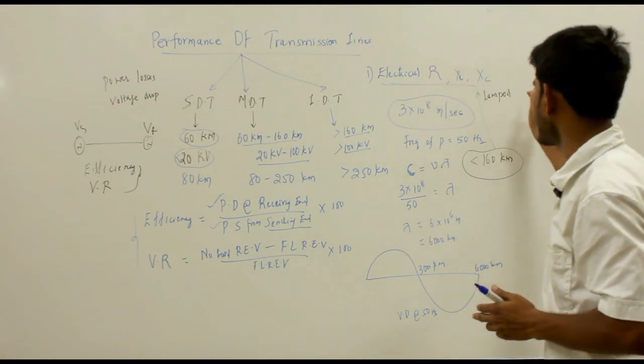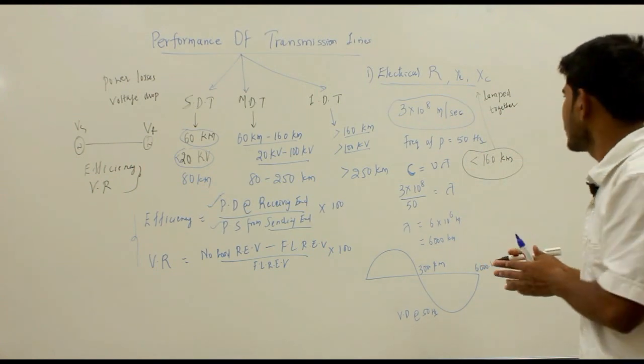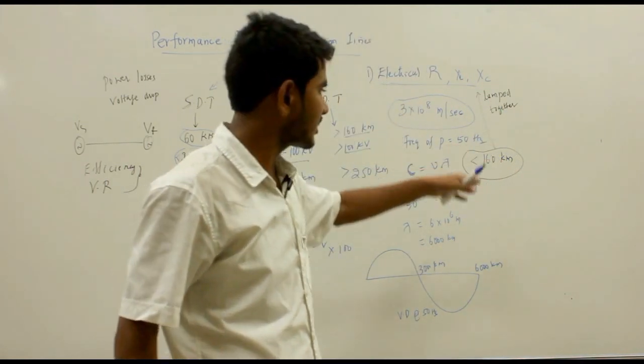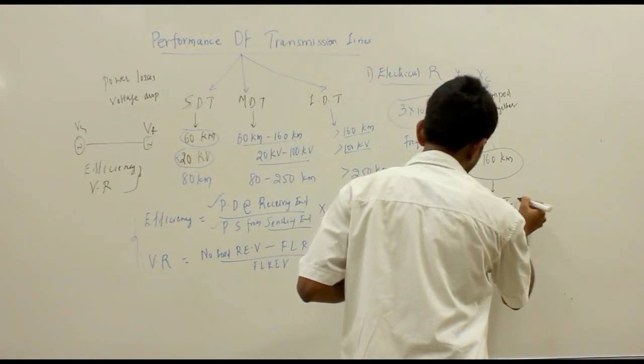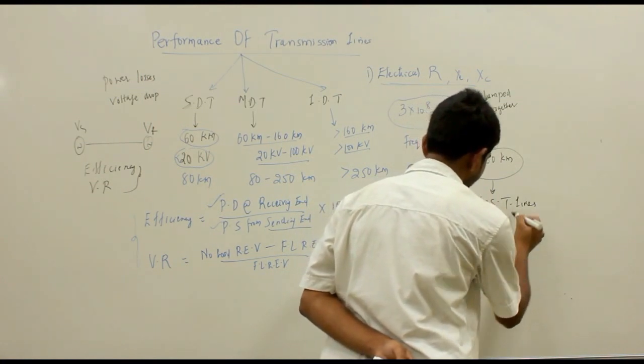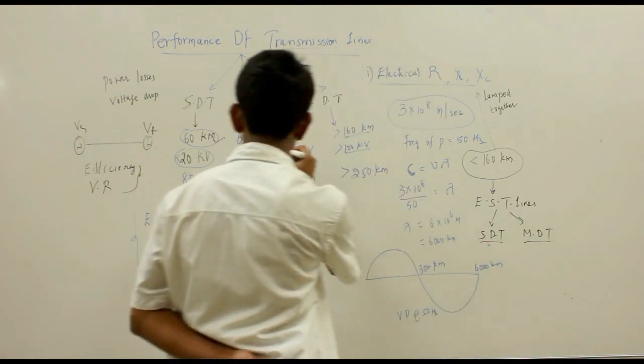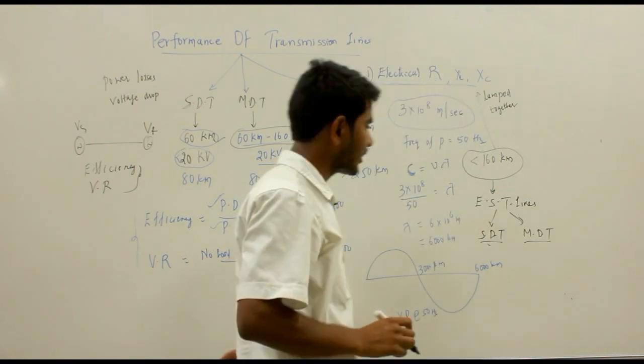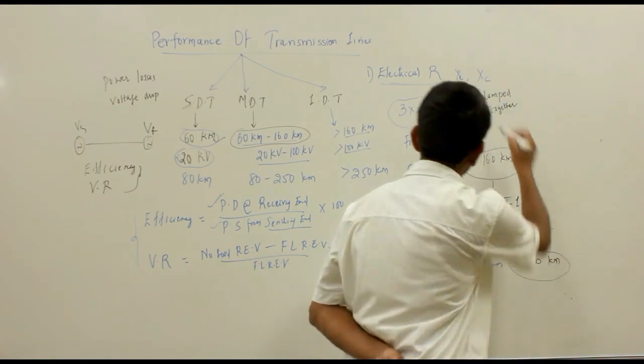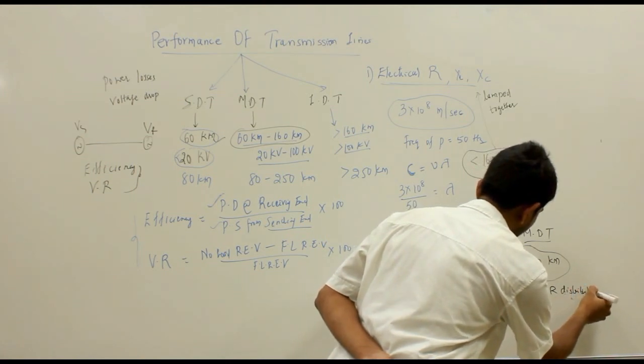For line lengths below 160 km, the electrical resistance, inductance, and capacitance are considered to be lumped together — meaning they are combined and placed together, not distributed. Hence, such lines below 160 km are referred to as electrically short transmission lines, which are categorized into the short distance (up to 60 km) and medium distance (60 to 160 km) transmission lines. For line lengths greater than 160 km, these parameters are assumed to be distributed, and such lines are referred to as long transmission lines.